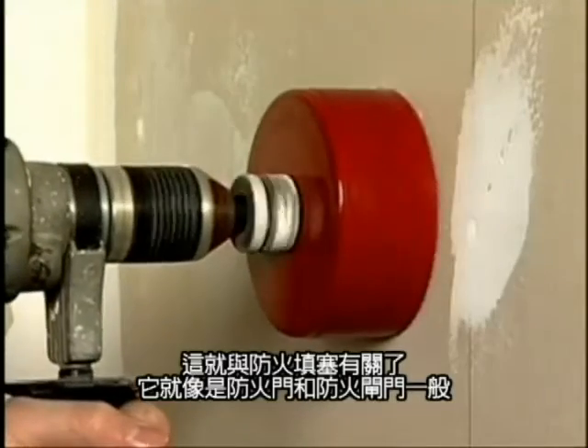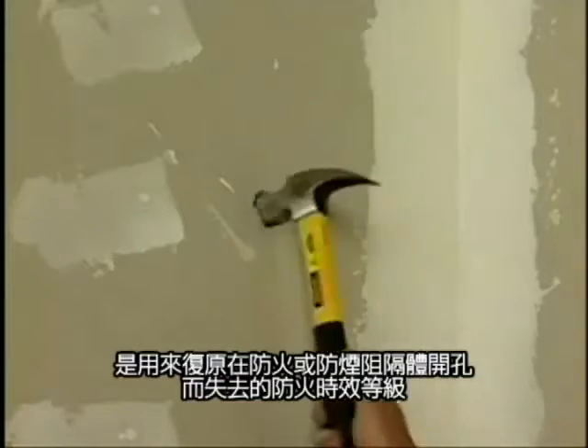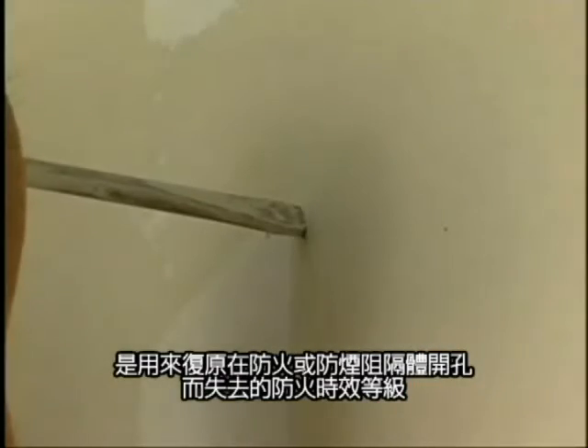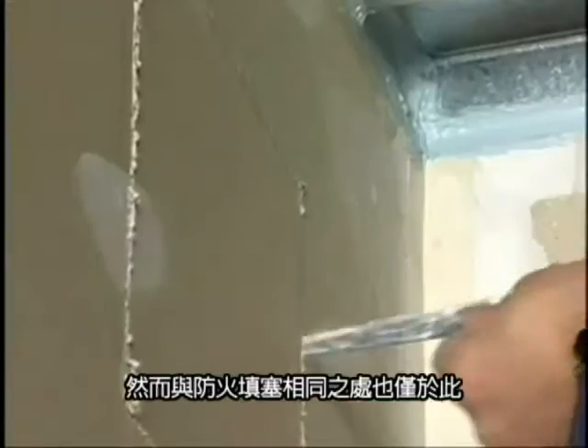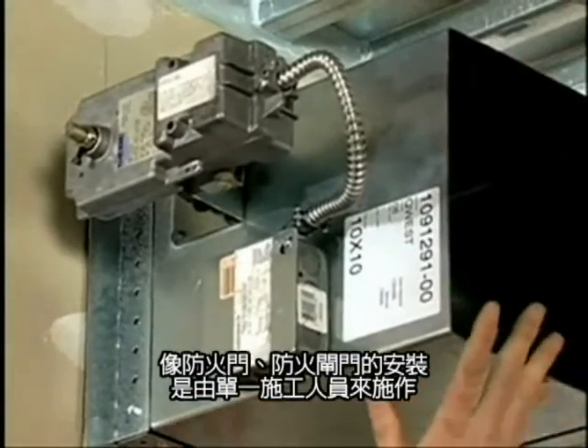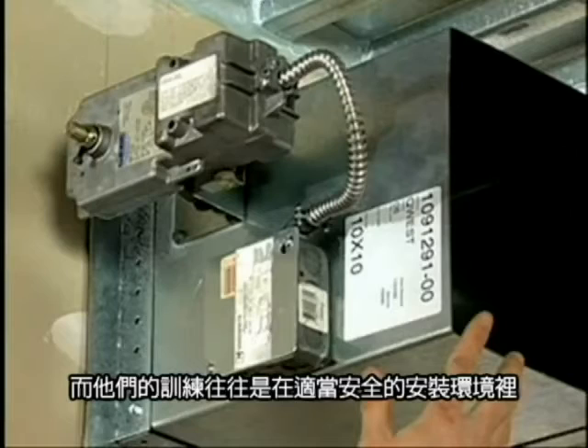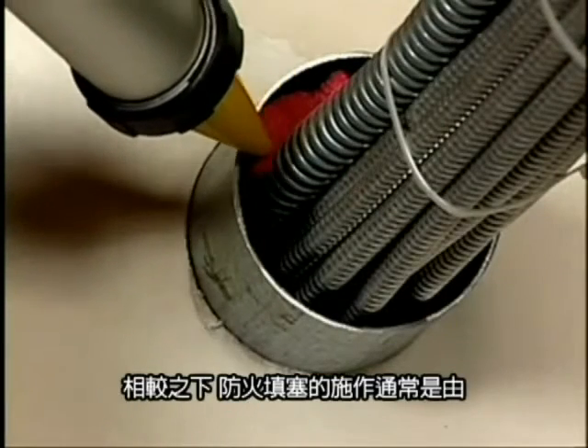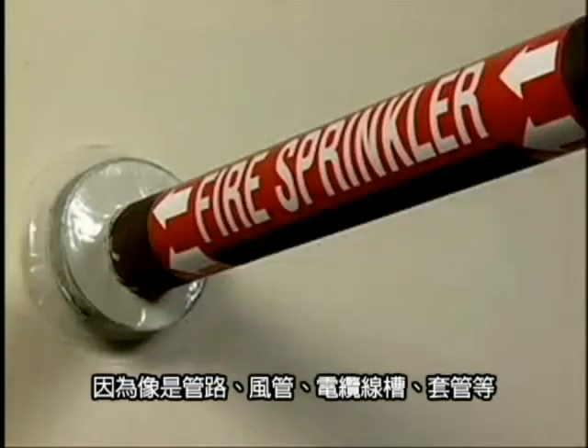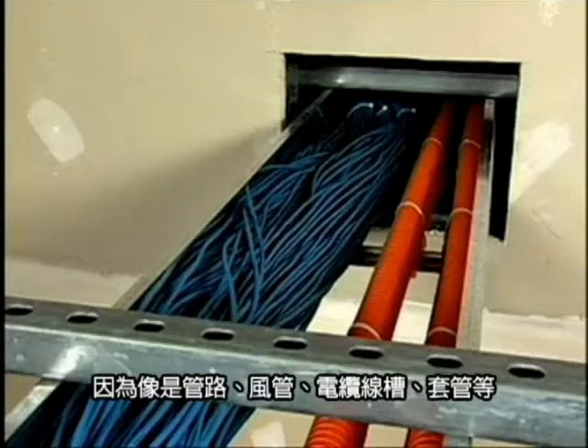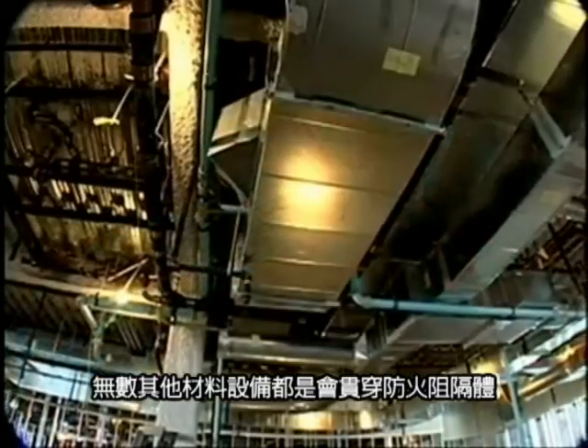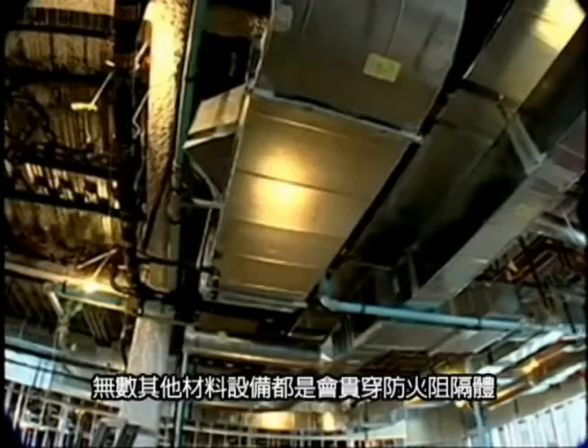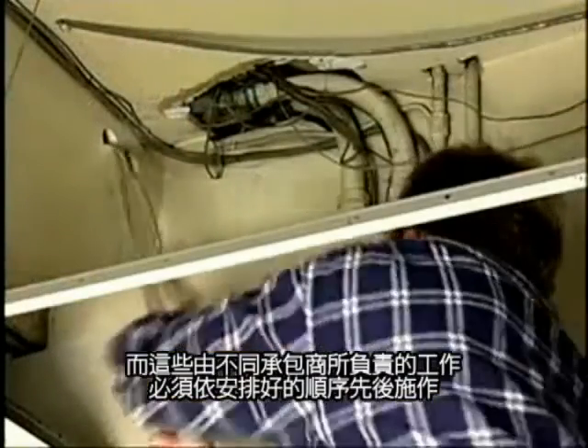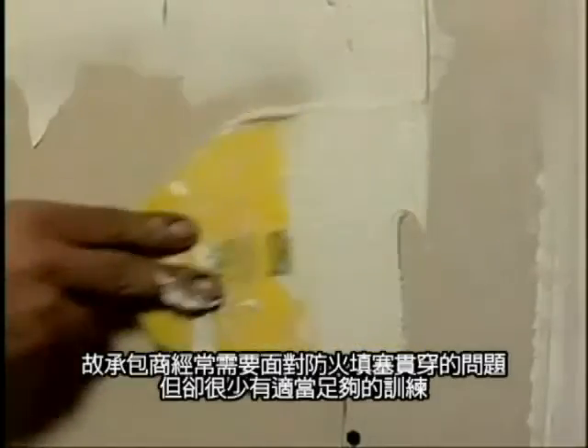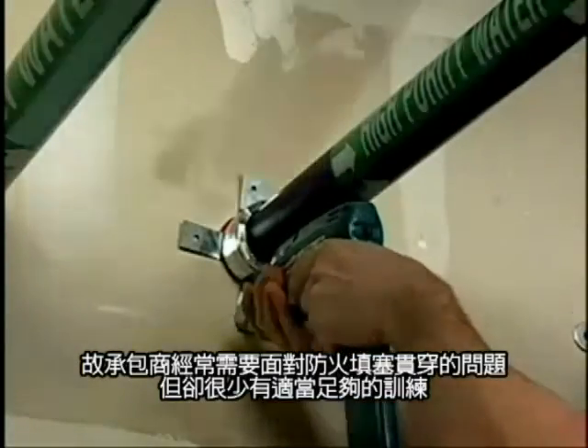This brings us to FireStop, which, like fire doors and dampers, is designed to restore the hourly fire rating that was lost when an opening was created in a smoke or fire barrier. The similarities, however, end there. Doors and dampers, for example, are all installed by a single craft, each of whom are trained in their proper and safe installation. FireStop, by contrast, is installed by nearly every craft because pipe, duct, conduit, cable tray, sleeves, and an infinite number of other service items all need to penetrate barriers. Because the work done by various sub-trades usually follows other crafts, these trades are often faced with fire-stopping penetrations as well, and rarely with adequate training.